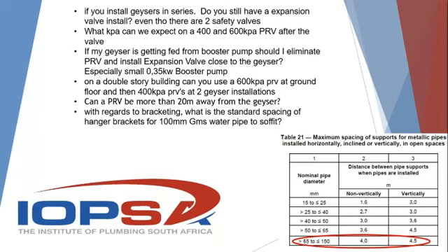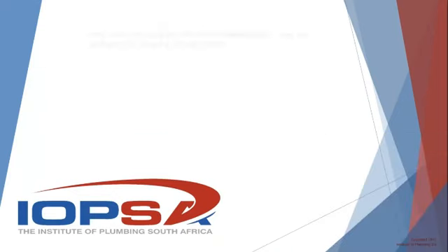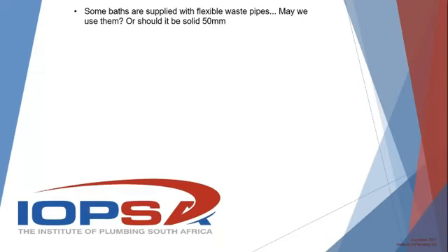In other words, suspended galvanized pipe, 100 mil. And there you can see table 21. That's in SANS 10252/1, and it gives you maximum spacing supports. So it can be less, but it cannot be more. For metallic pipes installed horizontally, non-vertically, 65 to 150 mil diameter pipe, 4 meter. So that's maximum. You're probably better served to go even a little bit less than that.